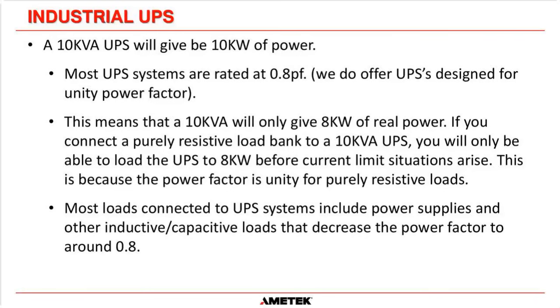The next misconception is a 10 kVA UPS will give you 10 kilowatts of power, and that is not correct. Most UPSs are rated at 0.8 power factor. You can buy a UPS designed for unity power factor, but a standard UPS is rated at 0.8 power factor. That means a 10 kVA UPS will only give 8 kilowatts of real power. So if you connect a purely resistive load to a 10 kVA UPS, you will only be able to load that UPS up to 8 kilowatts before a current limit situation arises. And that's because the power factor for that resistive load is unity, okay?